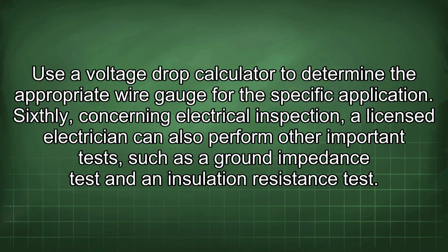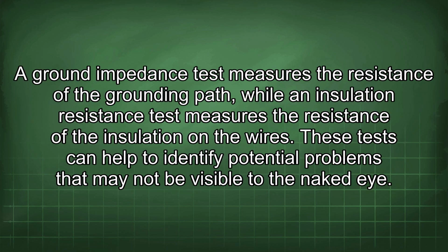Sixthly, concerning electrical inspection, a licensed electrician can also perform other important tests such as a ground impedance test and an insulation resistance test. The ground impedance test measures the resistance of the grounding path, while an insulation resistance test measures the resistance of the insulation on the wires. These tests can help to identify potential problems that may not be visible to the naked eye.